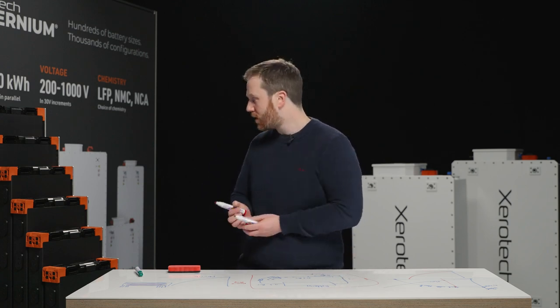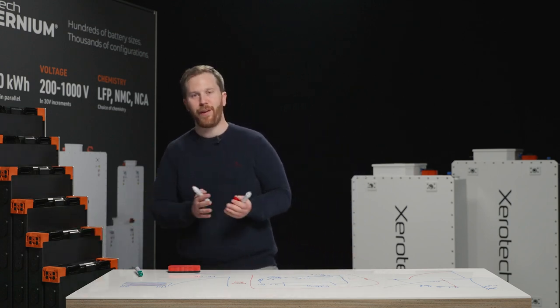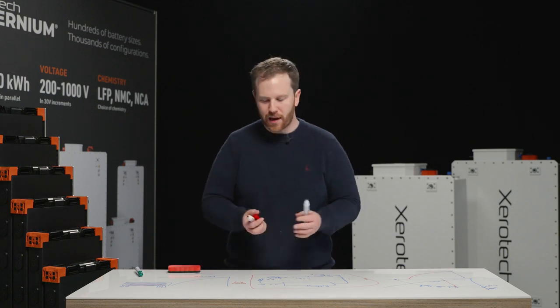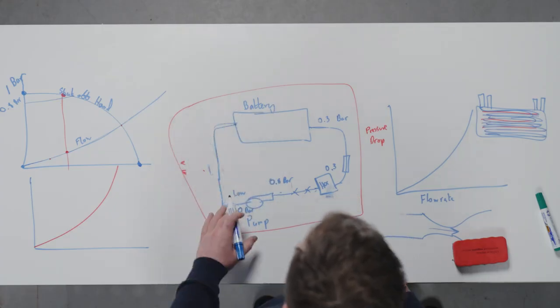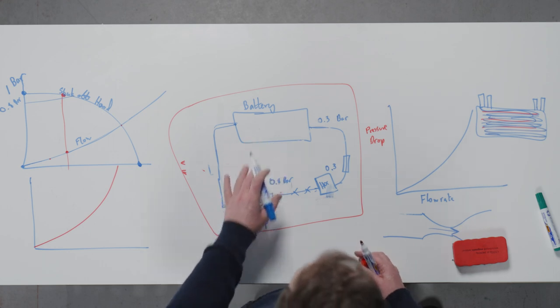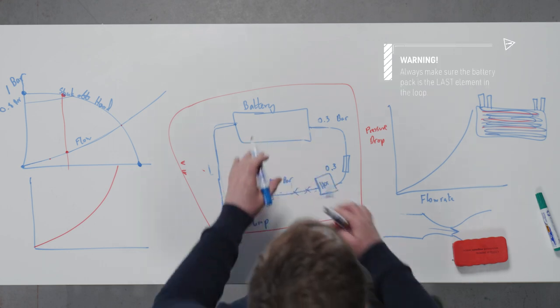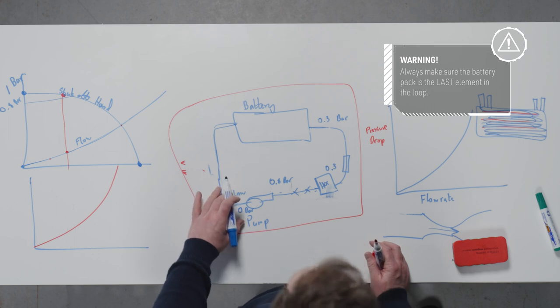The battery cooling system inside of our modules is an inflatable plastic duct. While it can operate at high pressures of several bar, for long-term durability and fatigue life, we prefer it to be operating at continuous pressures that are lower than that. So you want to minimize the continuous pressure that it's exposed to. And the way to achieve this is to simply position the battery pack as the last component before the pump in your system. This is incredibly important. You must put the battery as the final component.